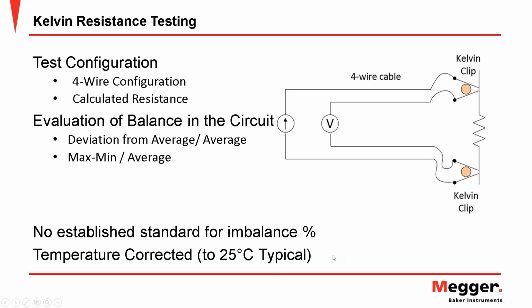So temperature correction is important because in a line-to-line resistance measurement, when we're measuring the resistance of a metallic circuit, like in this case, say copper or aluminum, those are directly related to the temperature, so that if temperature increases, that resistance will also increase and decrease as the temperature decreases. So it's important that we know exactly what it would be at a fixed temperature.